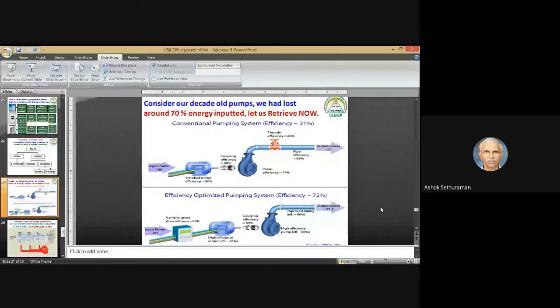That is why the government has said to replace the pumps. You can see that for 100 units given, only 30 units actually reach the destination - that loss has persisted for 30-40 years. Now, taking this step, we are able to replace the 30% efficient pump with a 70% efficient pump, replace the motor, replace it with a variable frequency drive, and also improve the piping.